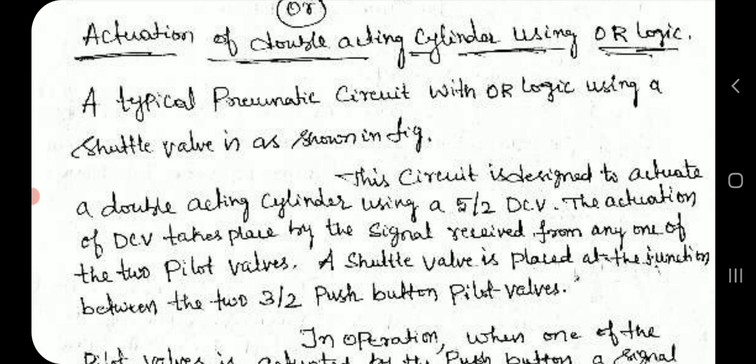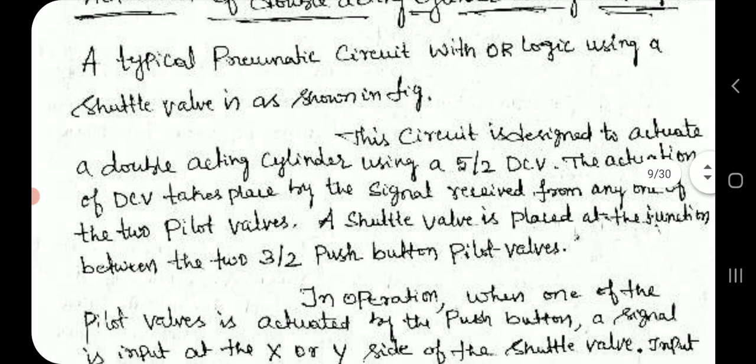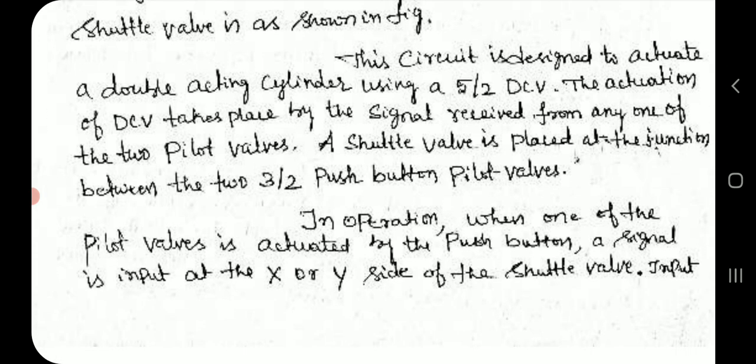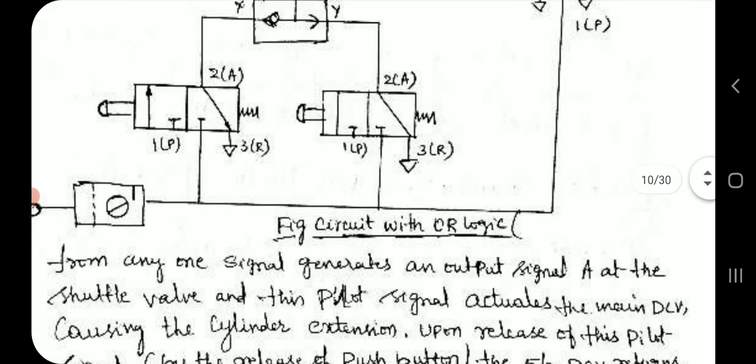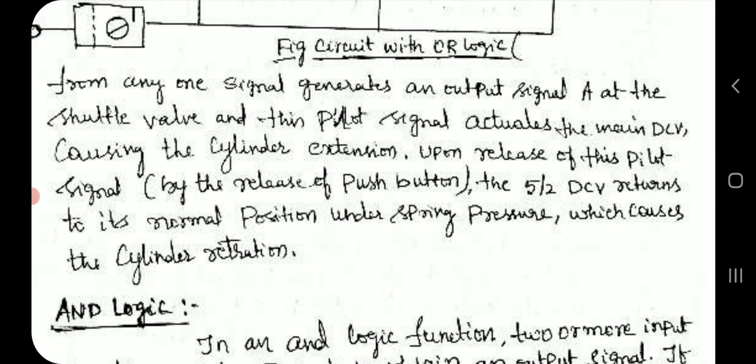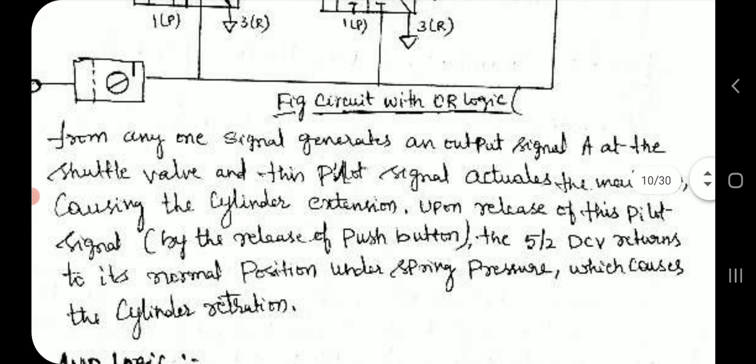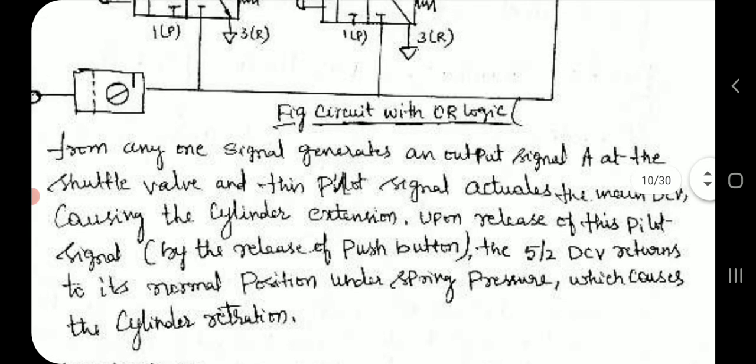A shuttle valve is placed at the junction between the two 3/2 push button pilot valves. In operation, when one of the pilot valves is actuated by the push button, a signal is input at the X or Y side of the shuttle valve.